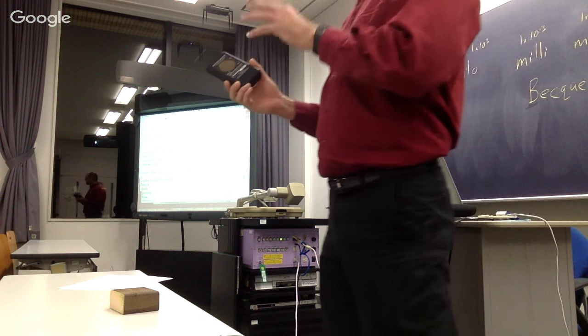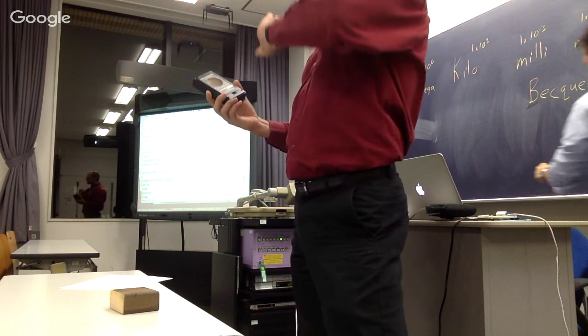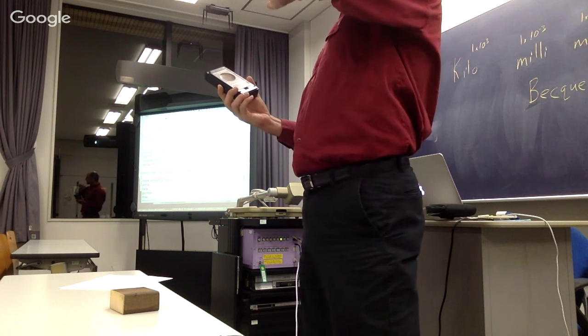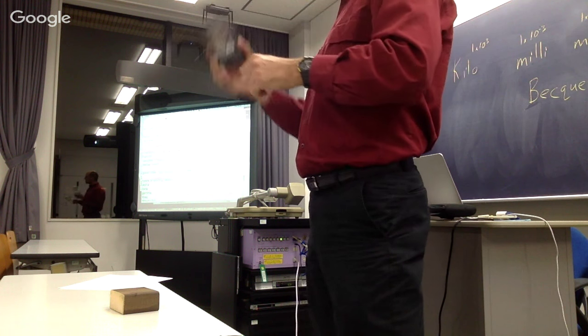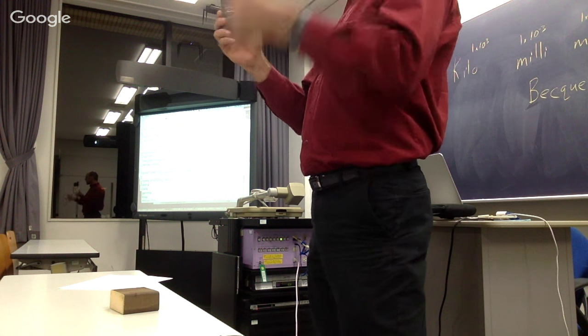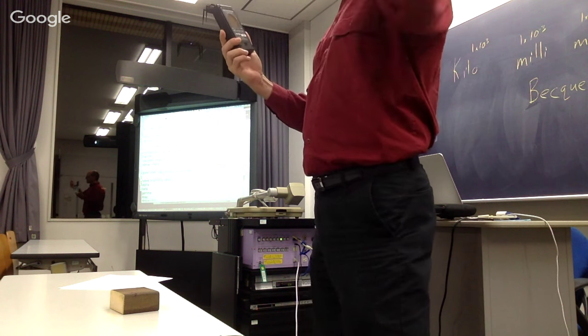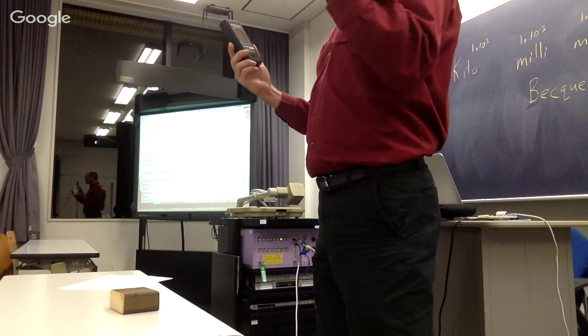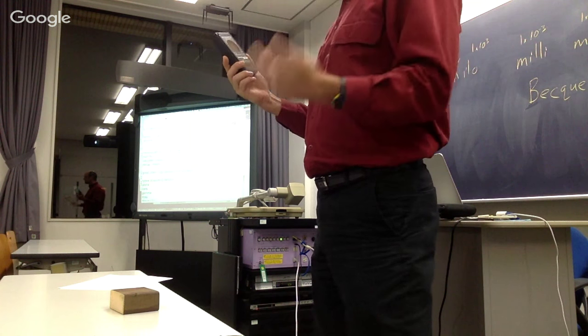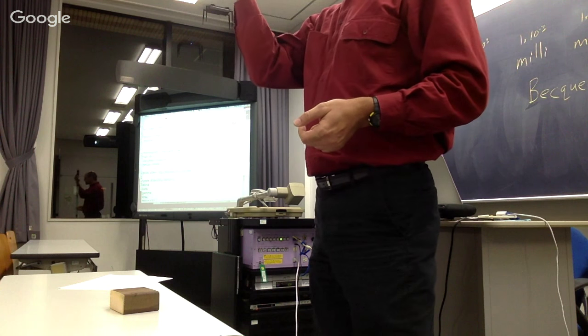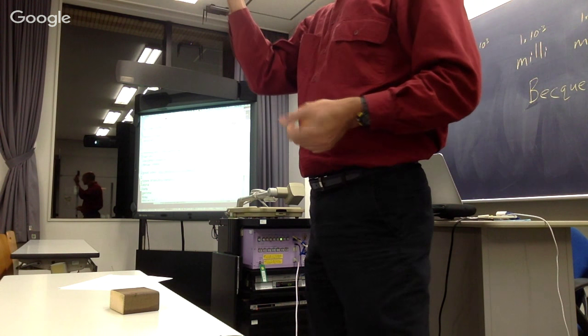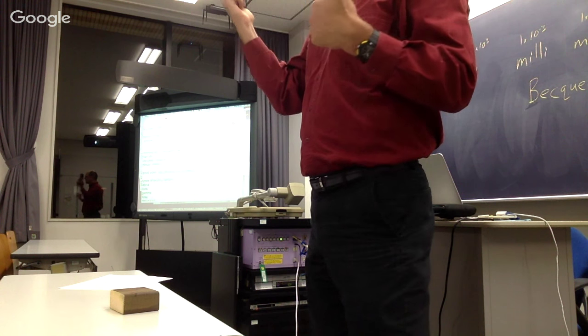So any type of radiation that is ionizing, that is able to strip one of those electrons and start that reaction, will discharge the tube and cause a click. And then the circuit in there charges it back up again, and the same thing can happen again. This happens very quickly, so it can actually happen tens of thousands of times a second if necessary. And the clicks you're hearing from this are because of random events that are happening all the time.